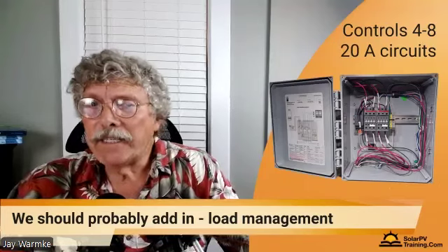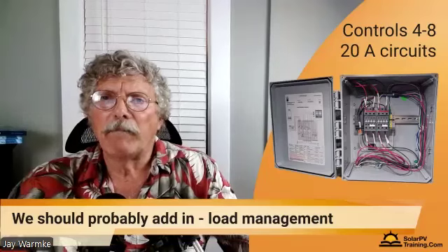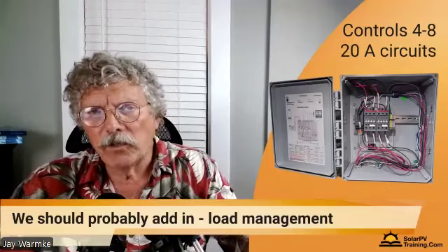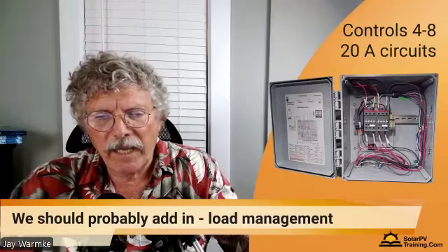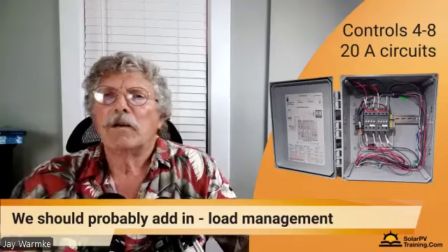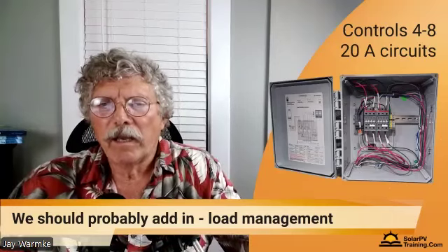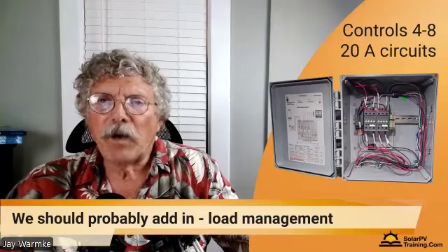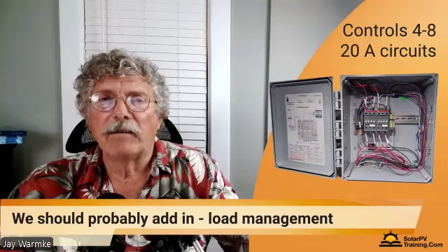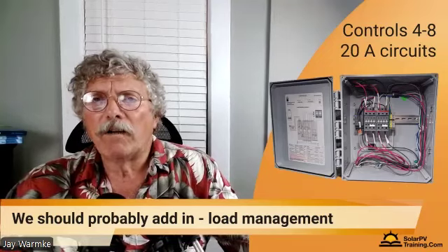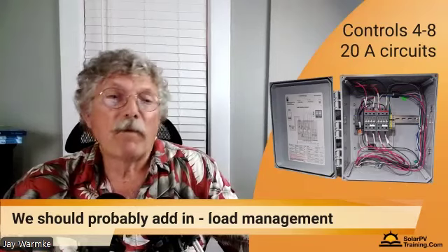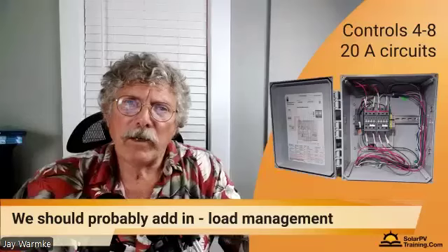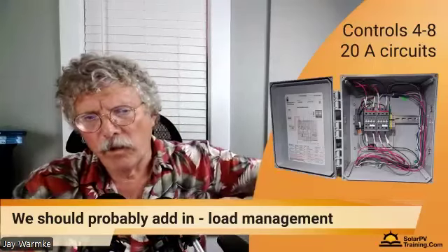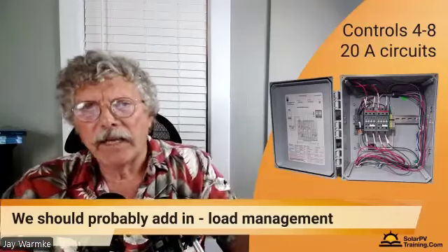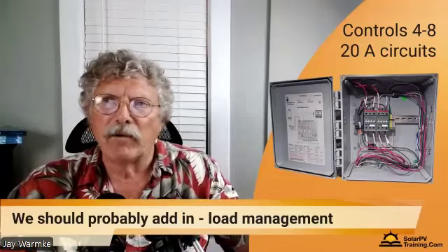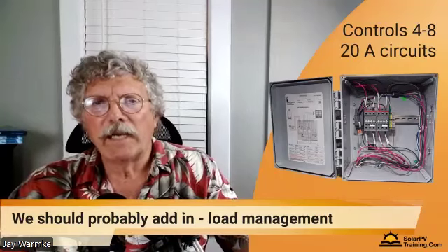But they are going to operate in tandem, and that's something that you need to understand, because this little system hooks into your smart switch, and in the smart switch, you can prioritize these loads. So conceptually, what you're dealing with here is you've got 4 loads here, but if you had 2 of these boxes, you'd have 8 loads. And you can say, which one do I want to turn off first if I'm running out of power? And then which one do I want to turn off second? And so on and so forth. And then which one is the highest priority? And that one you're going to keep on until the very last bit of power is drained. So you can prioritize those loads.